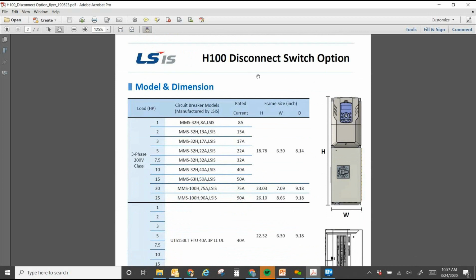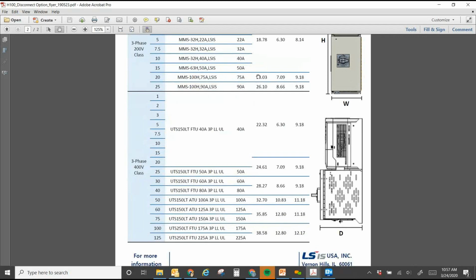That's a common spec in HVAC specs, they need 100K. If you look here, we use MMSs up to 25 horsepower for the 230 volt ones. That gives us 100K because we have combination ratings for our drive with the MMS. For the 480 volt ones, the higher voltage, we're using UTS 150 and 250 frame circuit breakers, and that gives us 100K as well.